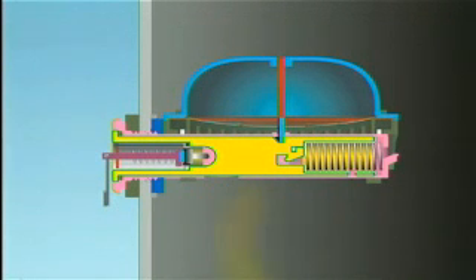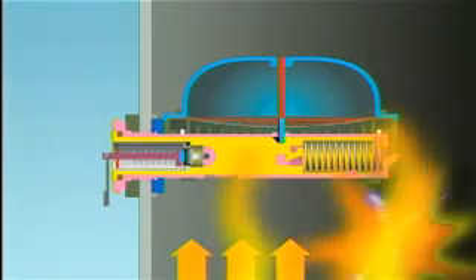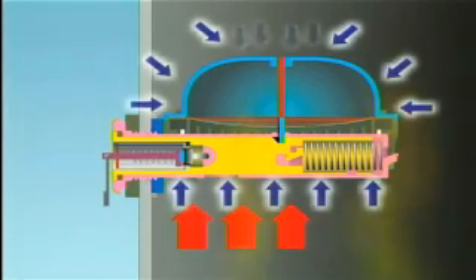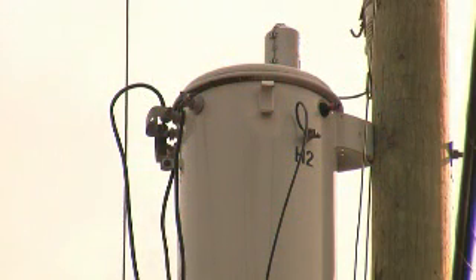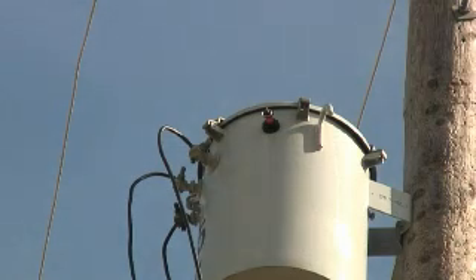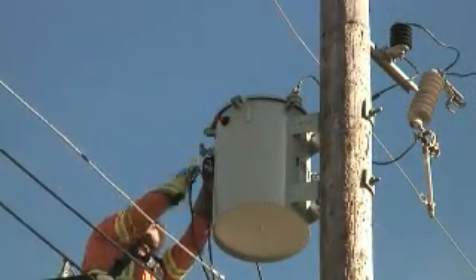When a fault occurs, there is a sudden increase in tank pressure, and these gases collect in and above the oil. If the internal fault is undetected and the transformer is re-energized, the risk of explosion increases. The explosion seen here is an example of one of the hazards line workers may face when re-energizing transformers that have an internal fault. To reduce the risk of significant events, utilities have developed thorough but time-consuming procedures.